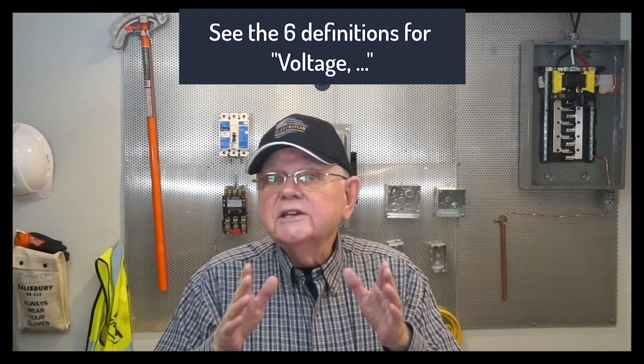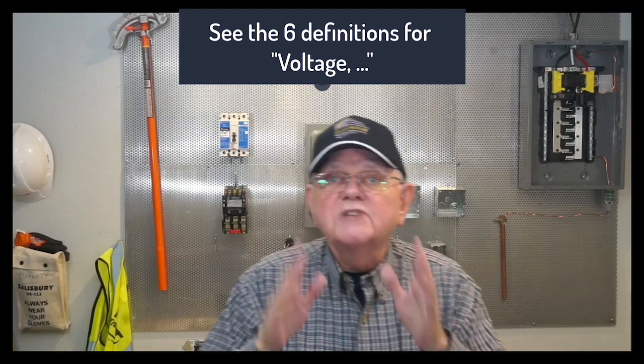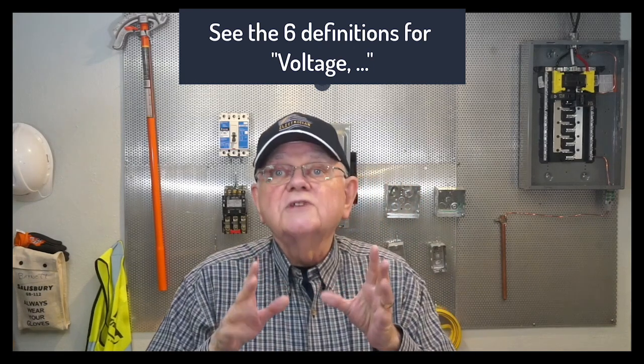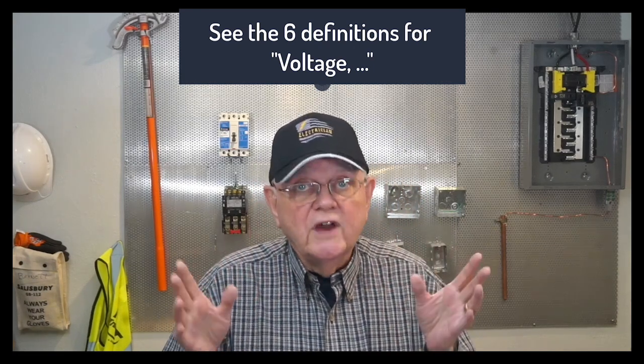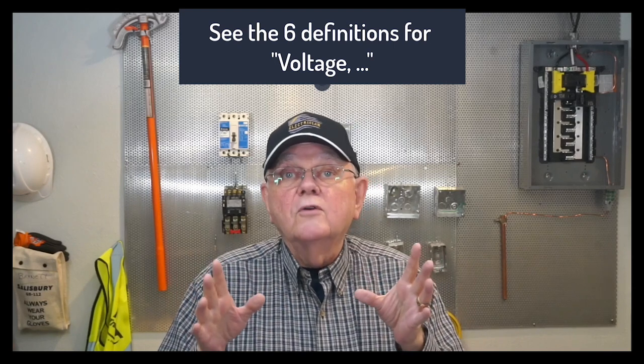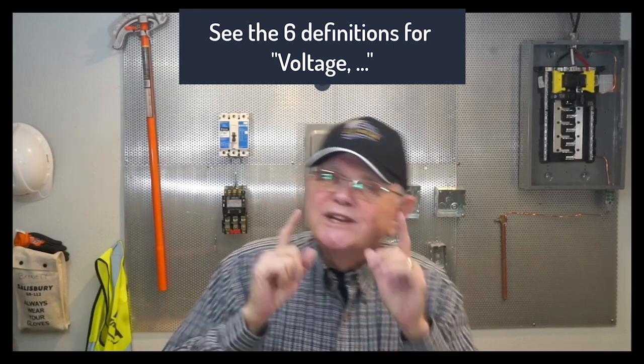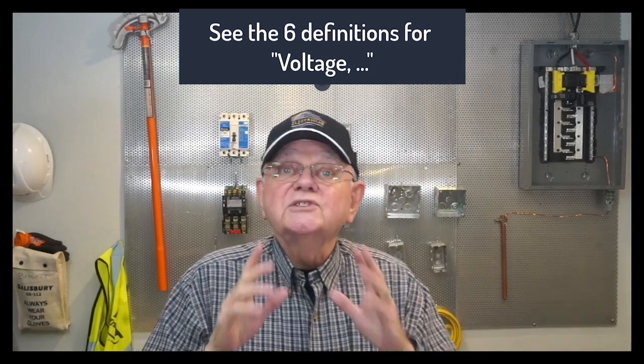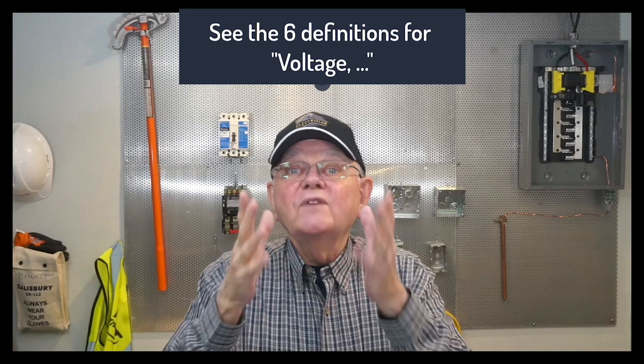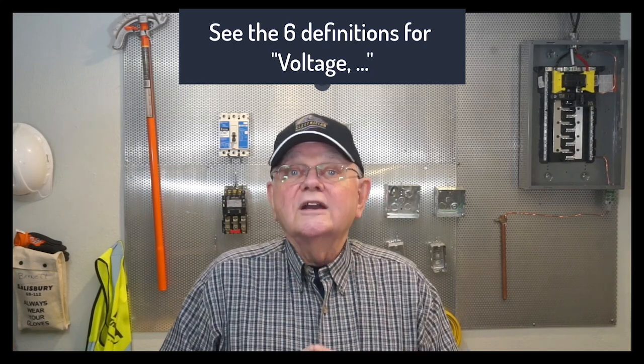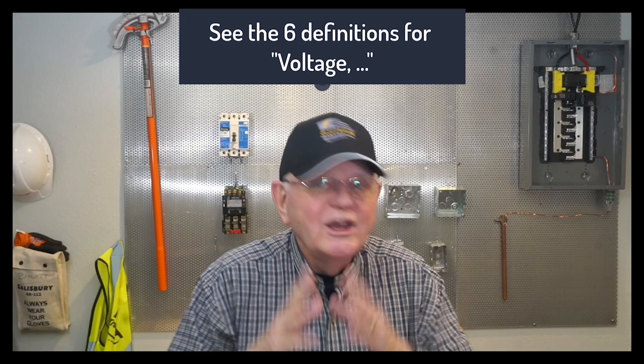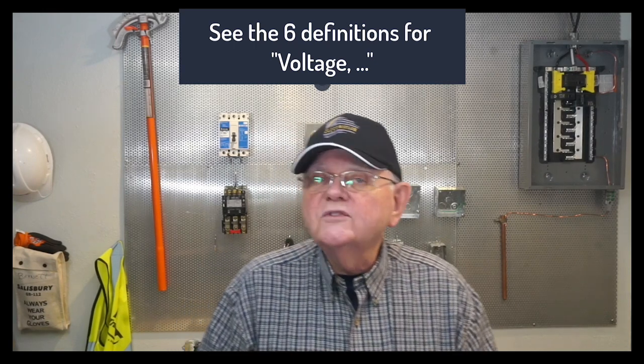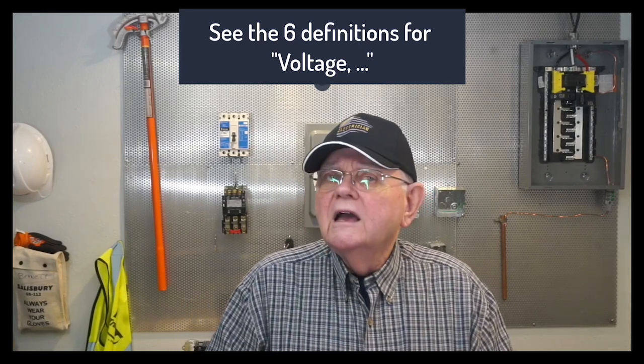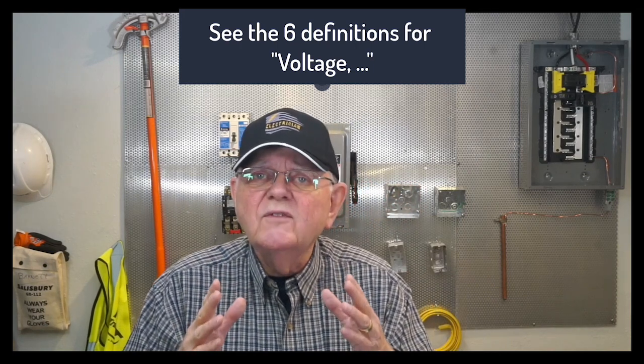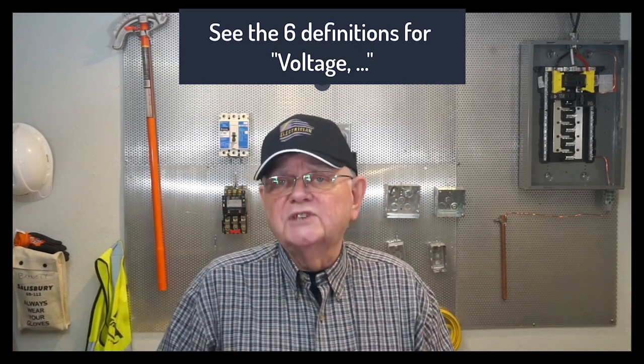But just read in the code book. It says high voltage, as far as they're concerned, a potential difference of more than 1,000 volts nominal. And that applies throughout the code. Now, there's an interesting informational note underneath that definition where it says that 1,000 volts up to 52 kV are commonly referred to as medium voltage. How many of you have 52 kV systems inside your facility?